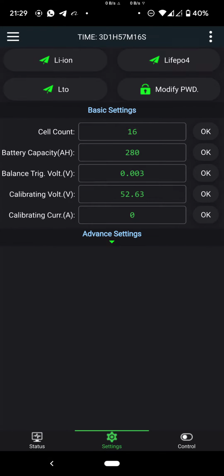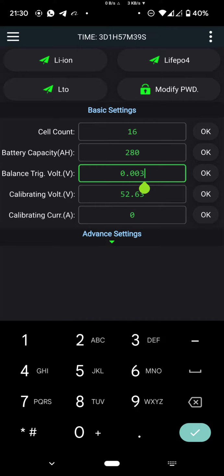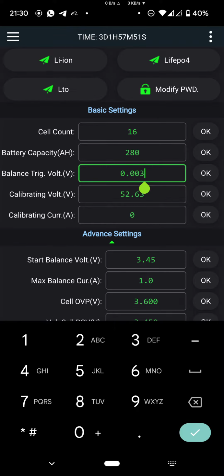Okay, now for the settings, it's the second tab. At the top we can see the chemistry type. Be careful to always check the parameters below if you click any of these chemistry types. Most parameters will reset, even these, capacity and trigger voltage for balancing. With previous versions of JK BMSs, these didn't usually reset. And below we have the usual parameters and some new ones. I will only talk about the new ones, most of them, and give some recommendations.